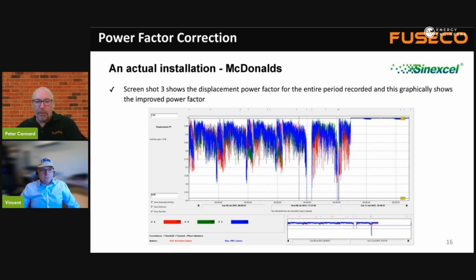So here we're looking at power factor itself. Power factor is a relationship between kilowatt and kVA. From the old maths, using SOHCAHTOA on the triangle, the relationship between kilowatt and kVA gives you cos phi—adjacent over hypotenuse, kilowatt over kVA. Cos phi should be 1 if they're the same length, and once you get that angle, you get a cos phi. Cos phi is power factor. When you turn on the power factor correction unit, it goes from up and down, up and down, to over on the right-hand side where it's close to 1. It's not perfectly 1.